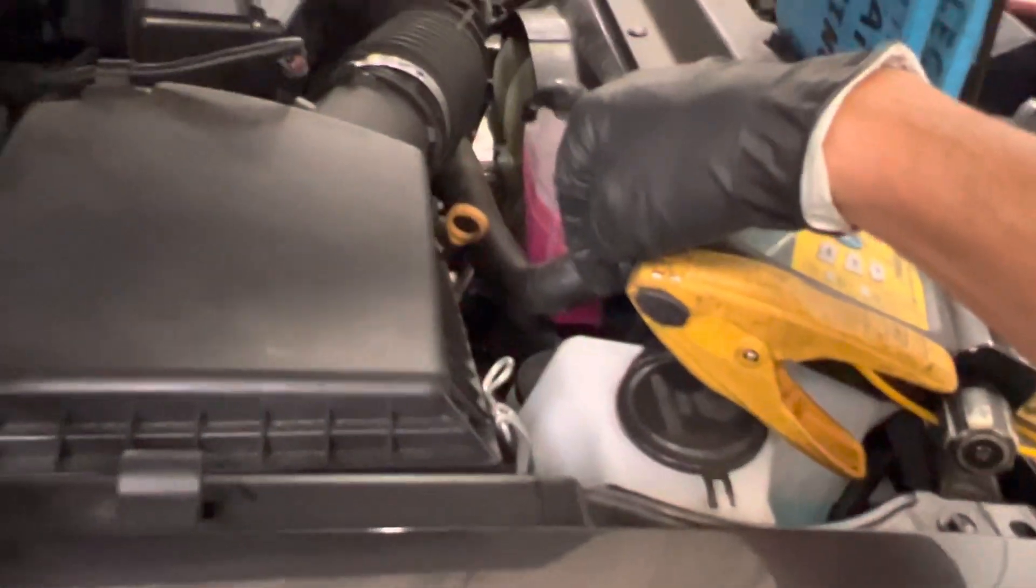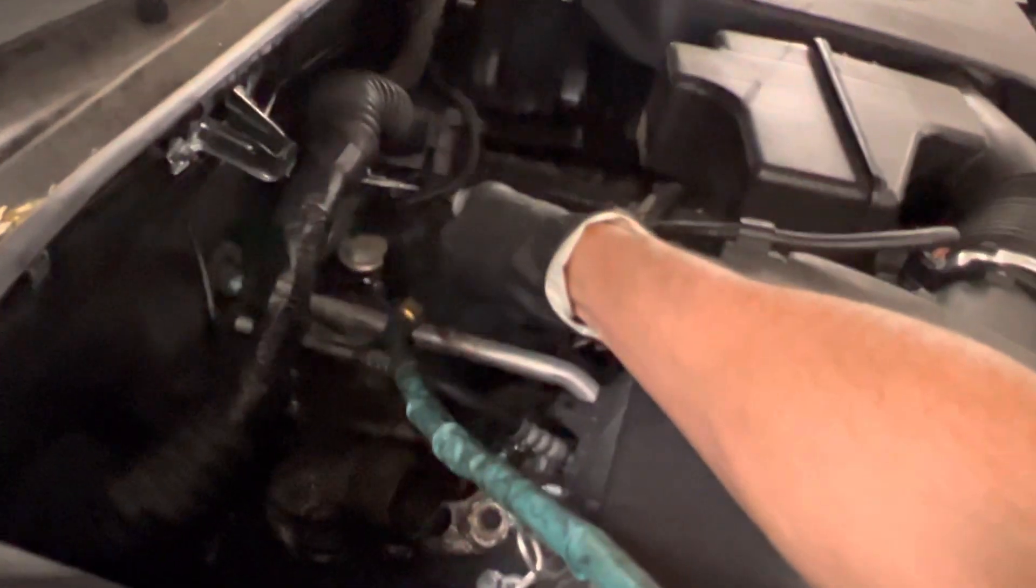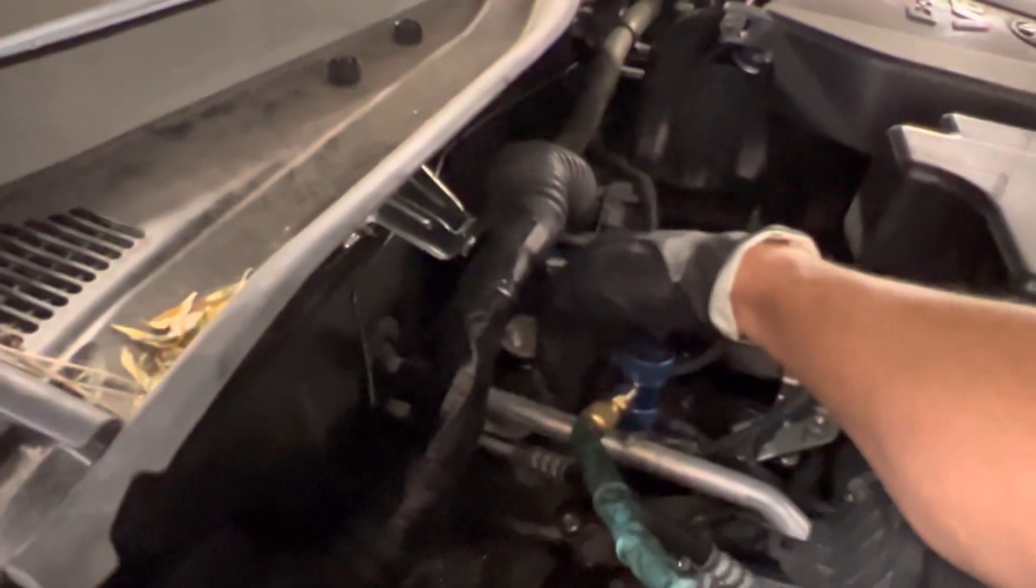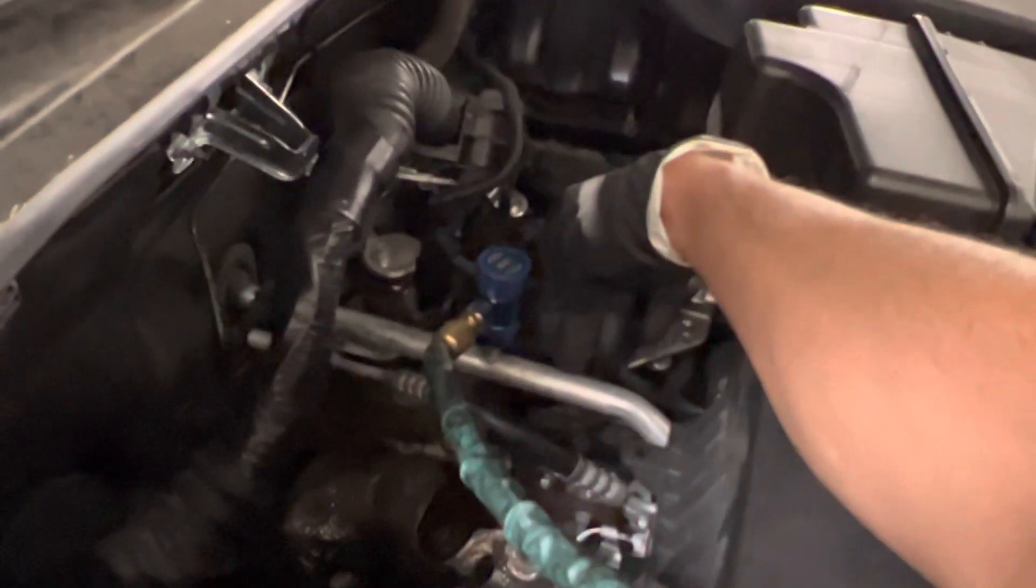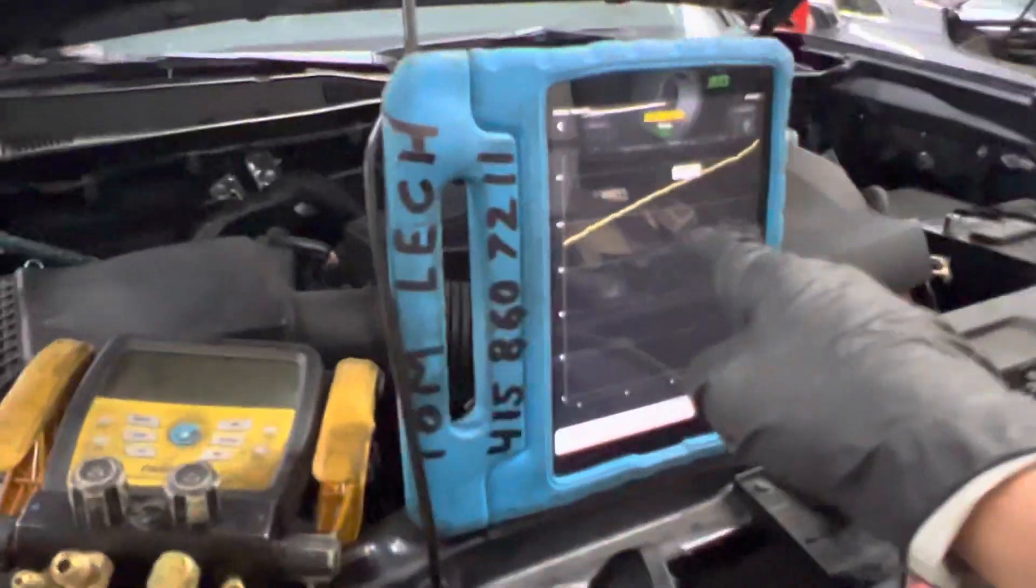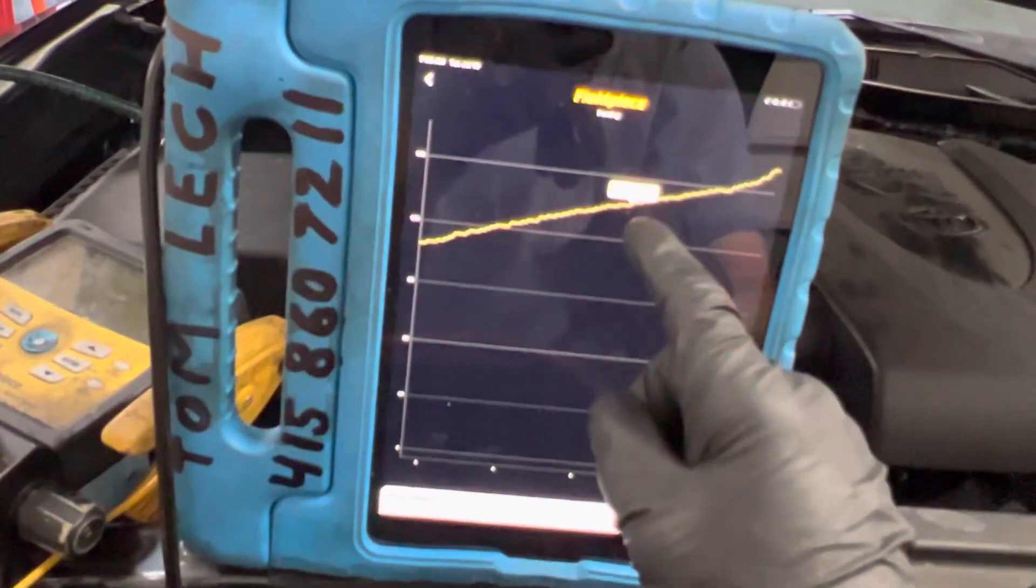If I removed the gauges and only used silicone vacuum going directly to a Y branch with shut-off isolation valves right at the hoses, and had my micron gauge attached at a third location or off adapters, you would not see this rapid decay as fast.